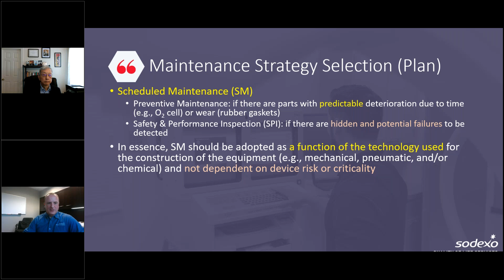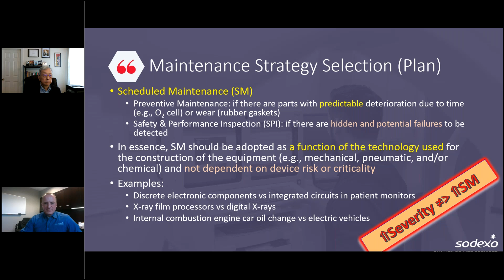So maintenance strategy planning, we're looking at scheduled maintenance. These are parts with predictable deterioration. Again, the preventive true PM, safety and performance inspections are the other type of planned maintenance. Those are there really to catch any of the hidden or potential failures. Ensure that your scheduled maintenance is adopted as a function of technology used. So again, examples of that are ventilators, very mechanical. It's going to have a lot of moving parts, a lot of replacement parts. Old school film processors, I haven't seen anybody doing silver recovery in quite some time. So that's saving us a lot of time and energy once we switch to digital x-rays. Again, increased severity does not necessarily mean we're going to increase scheduled maintenance.